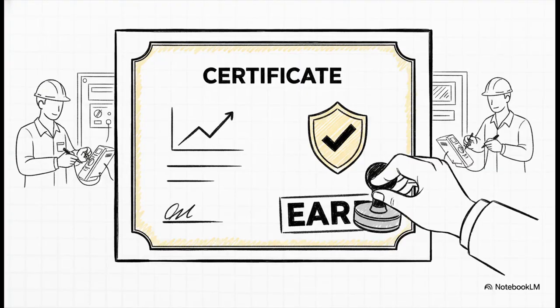You don't just flip the big switch and hope for the best. No, every single hardwired UPS system has to go through incredibly rigorous testing and get certified by qualified engineers. They literally bring in special equipment to fake power outages, to create overloads, to simulate short circuits, and they measure every single response. It's all about getting that documented proof that this system is absolutely ready for a real crisis.